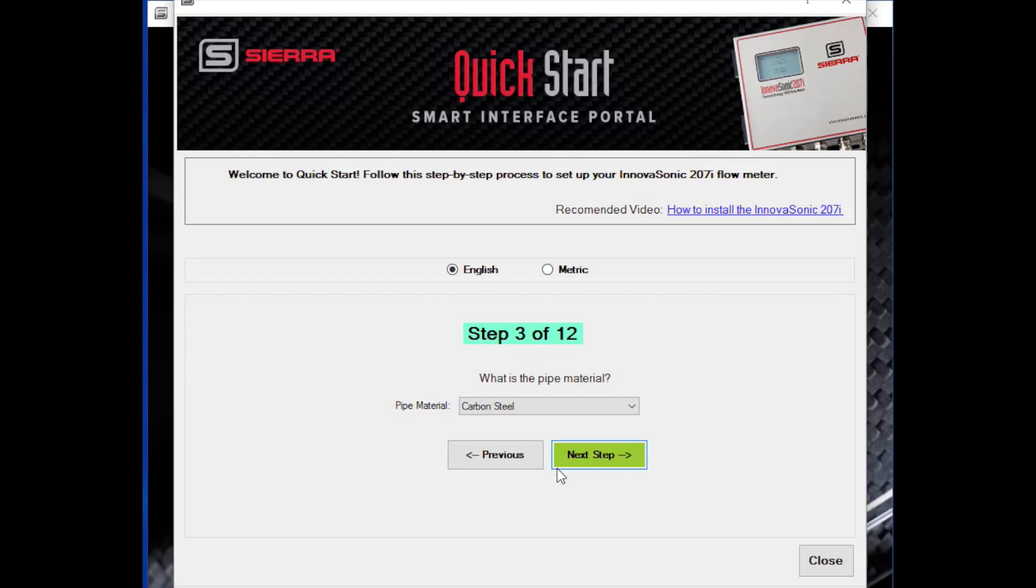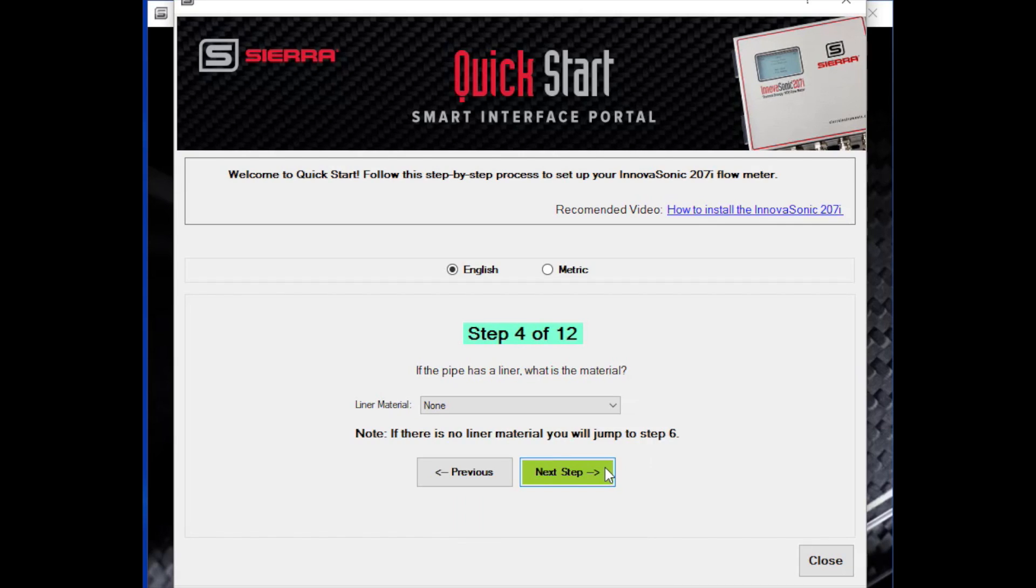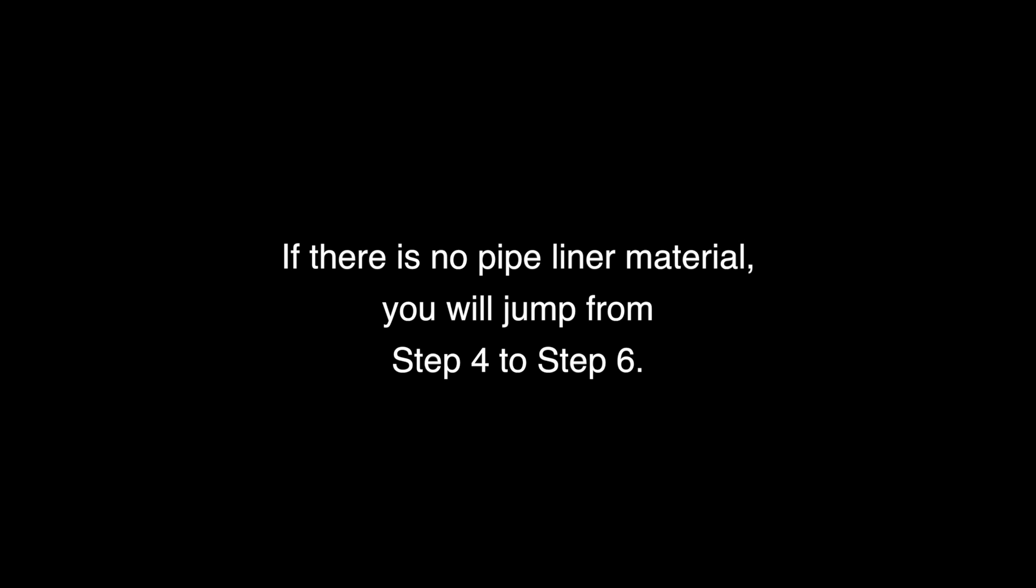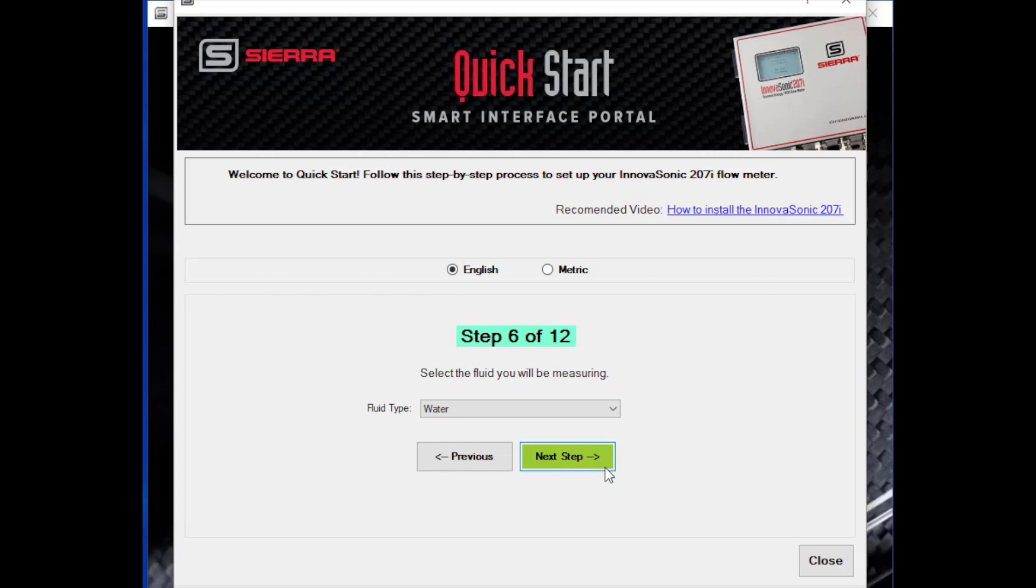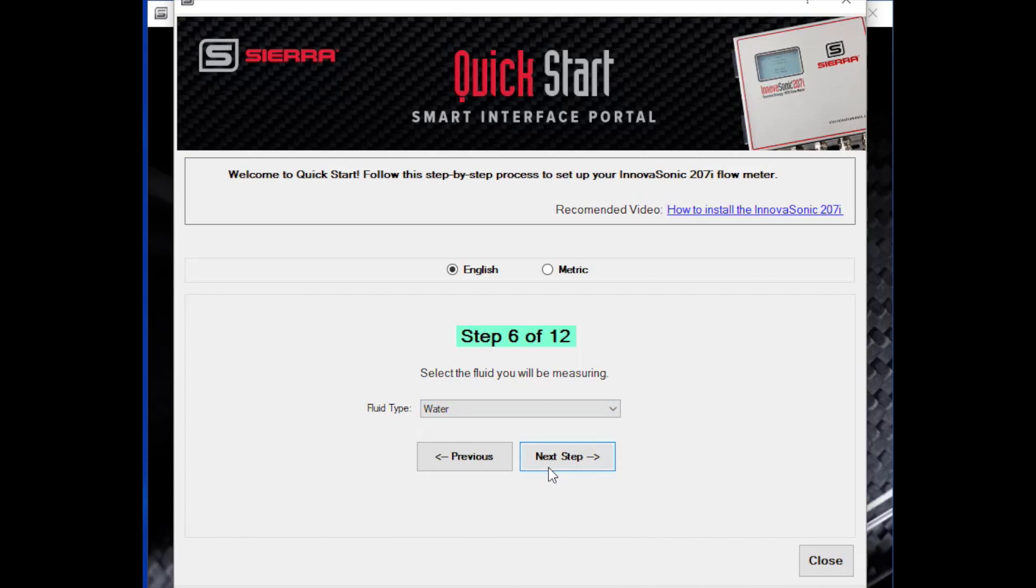Step three is what is the pipe material. There's a drop-down menu of various materials that a pipe can be made out of. Step four is if the pipe has a liner. Some pipes have a liner on the inside to cut down on rust and things like that. The next step is what's inside the pipe. What are you measuring? Usually that might be water, but there are a lot of other fluids in the pull-down menu that you can look at. Kerosene, oil, peanut oil, lots of different ones. So select the fluid that you want to measure and proceed on to the next step.